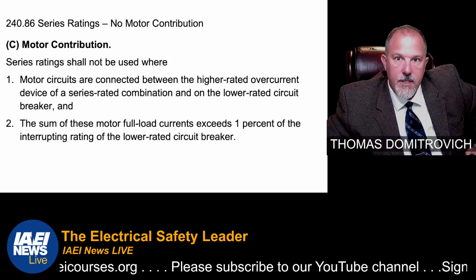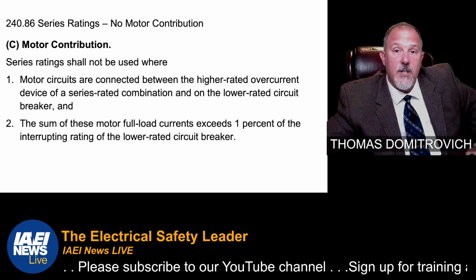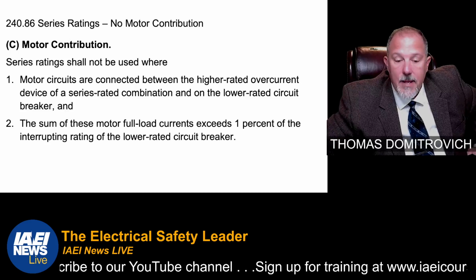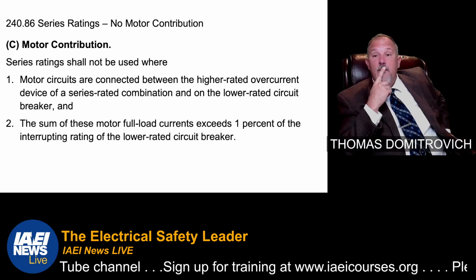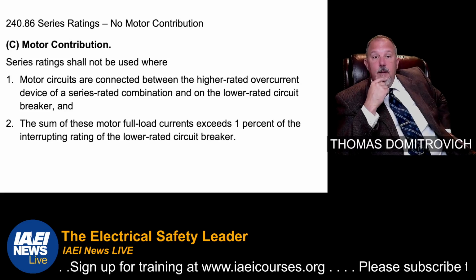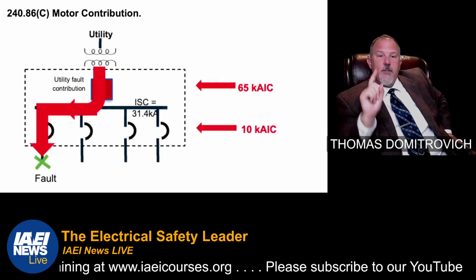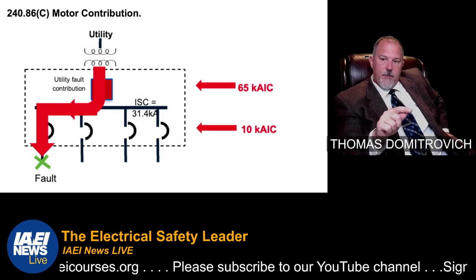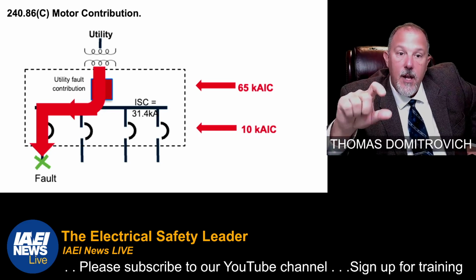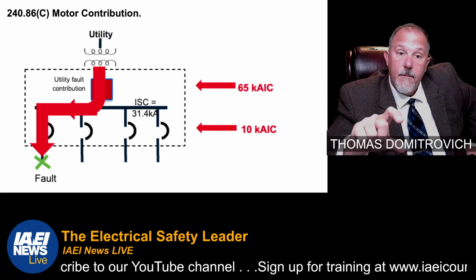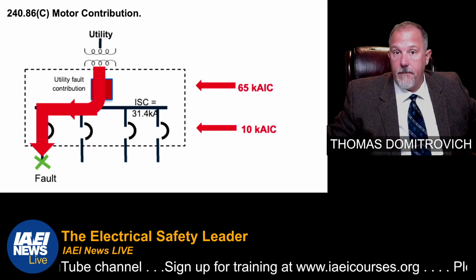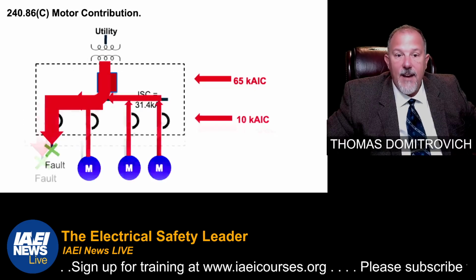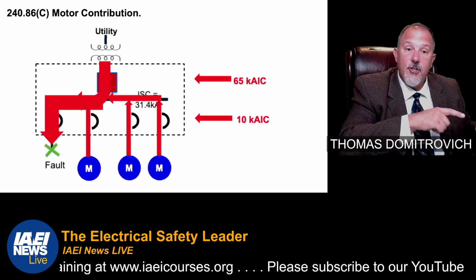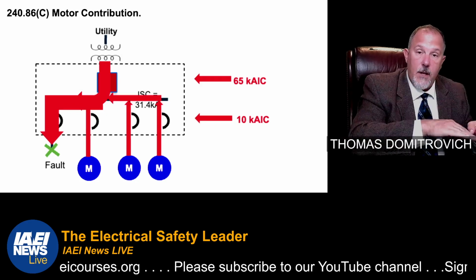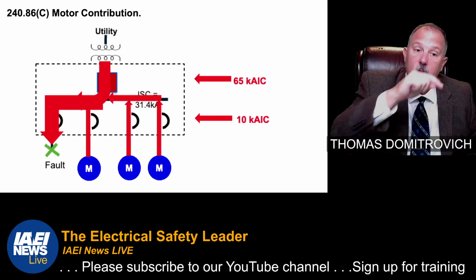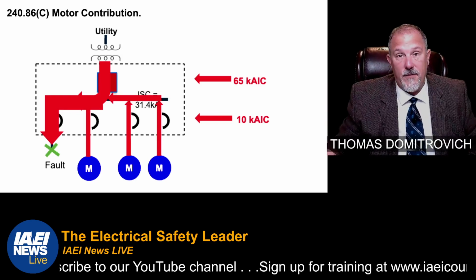And you don't get selective coordination with a series rated system. So if you see a series rated system and it's an Article 700 system, red flags go off. Now, motor contribution. This is what's missed very often, and I'll show you why. In a series rated system, when I have an upstream device and a downstream device, those devices are tested in pairs. Both devices see the same current, and they will both open to clear the fault together. But if I have motors and motor contribution, the downstream overcurrent device, because of the way the currents flow, is going to have more fault current passing through it than the upstream overcurrent device.